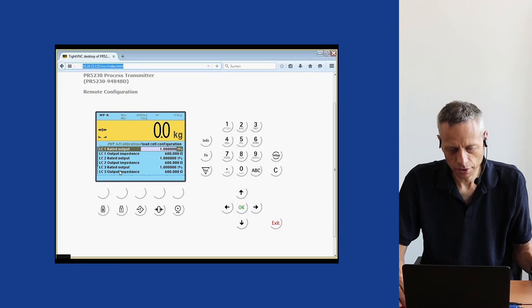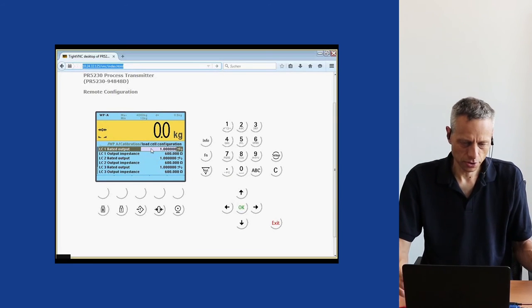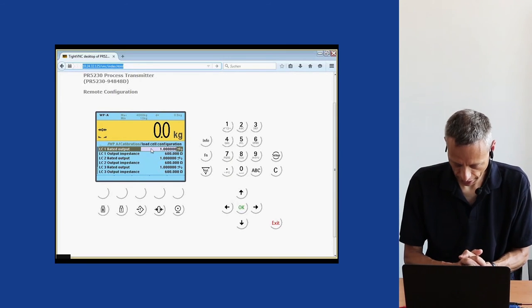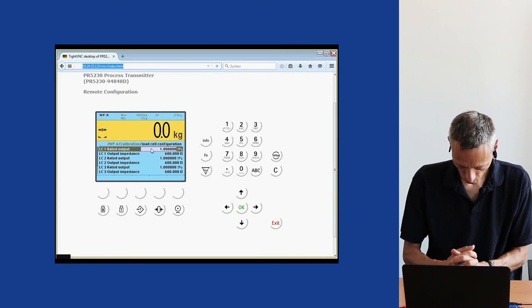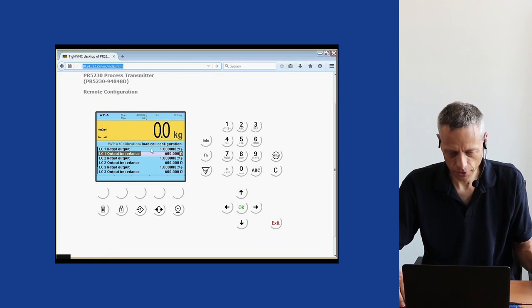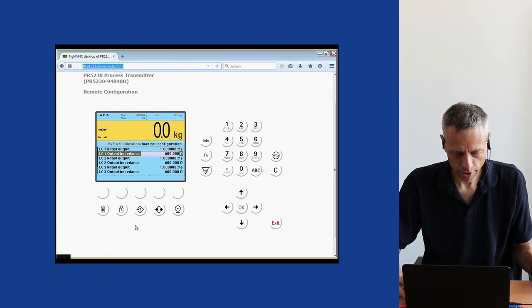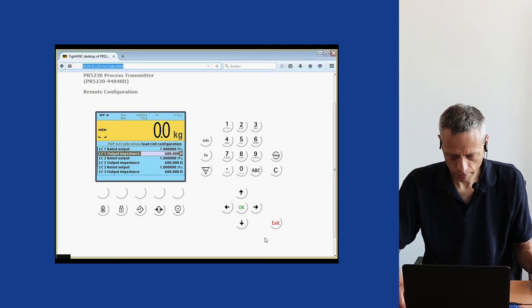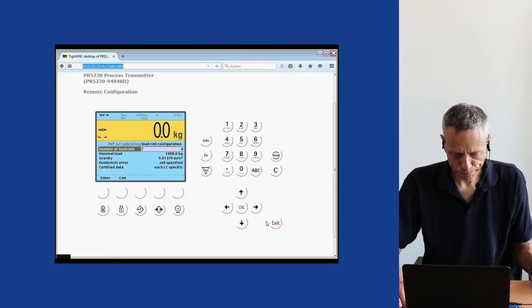These values can deviate from 1 mV/V — for example, they could be 0.99976. In the same way, the output impedance of a load cell can vary, so we can enter up to 4 load cell data sets here. In this case we don't change the values, as this is just a demonstration. We then confirm with Enter, having all the data for calibration.